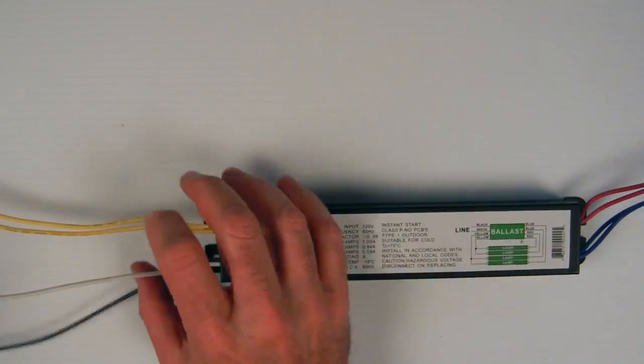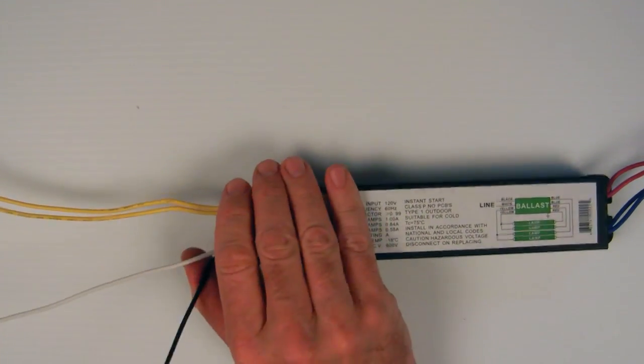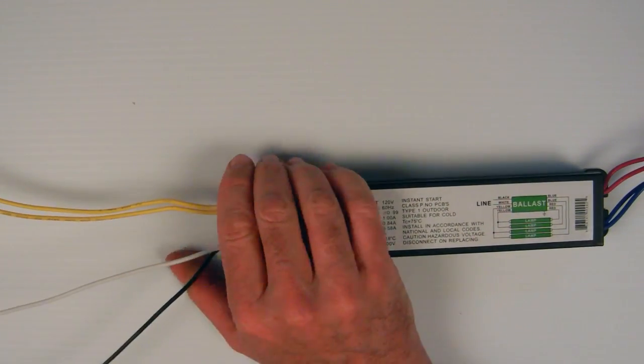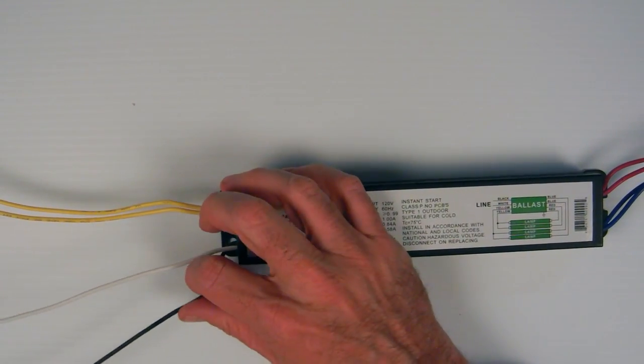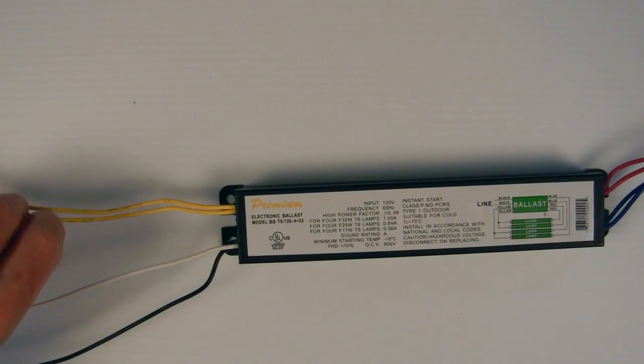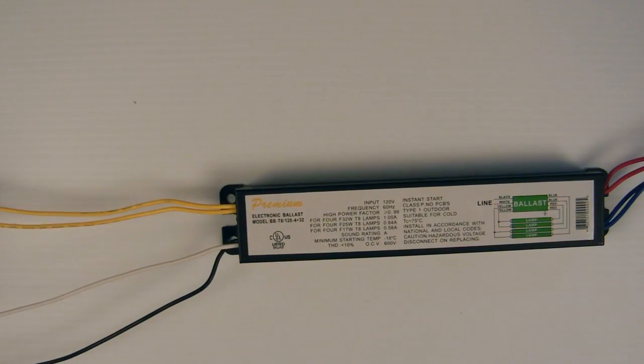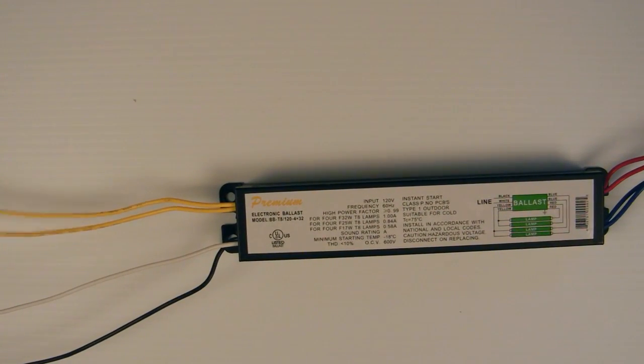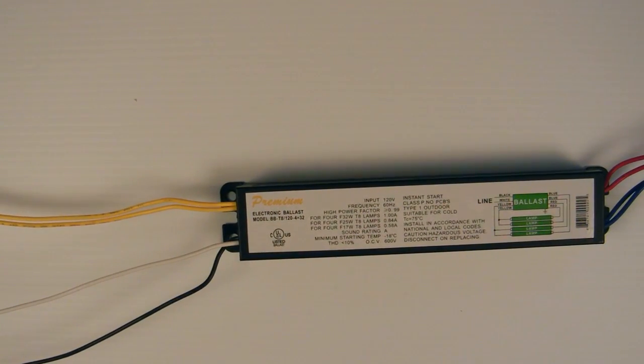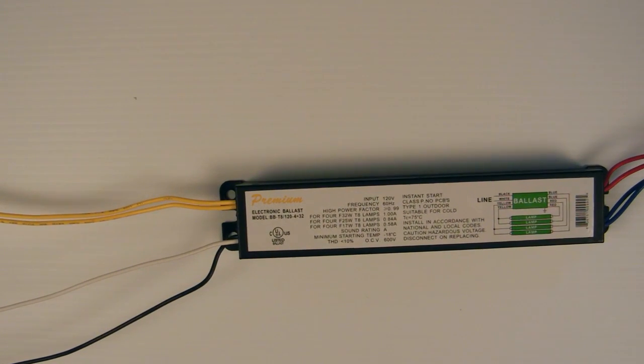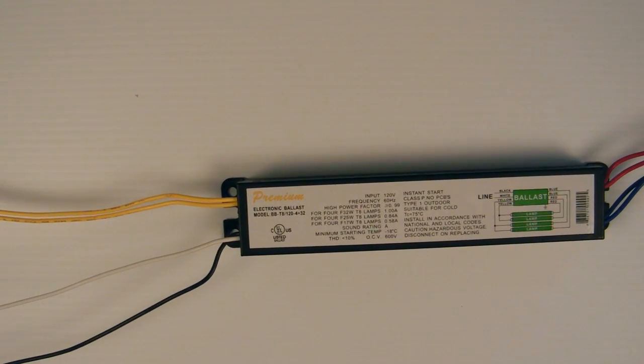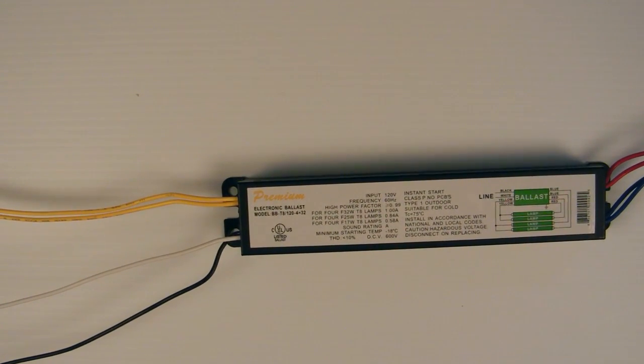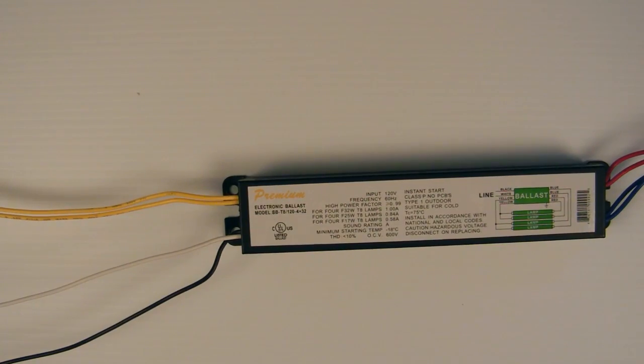Remember, the white wire here is always a neutral. Black is always the hot or the power. And the other wires go to the ends of the fluorescent tubes, which have what they call a tombstone. That's where the tubes connect electrically to the wires and to the bulb.